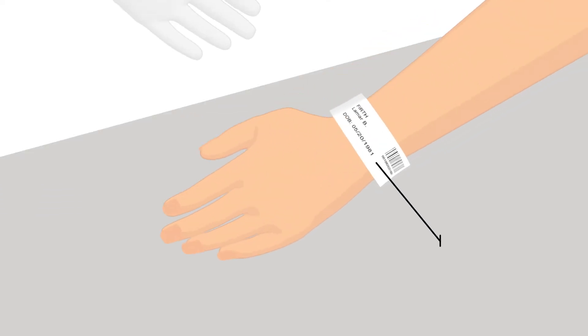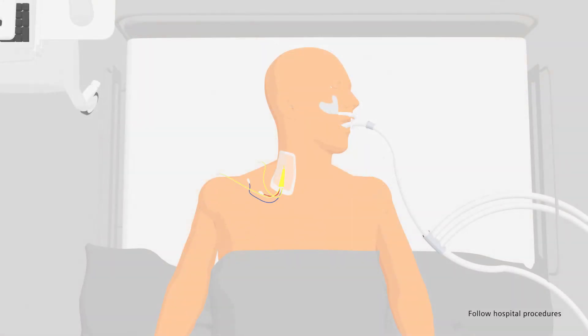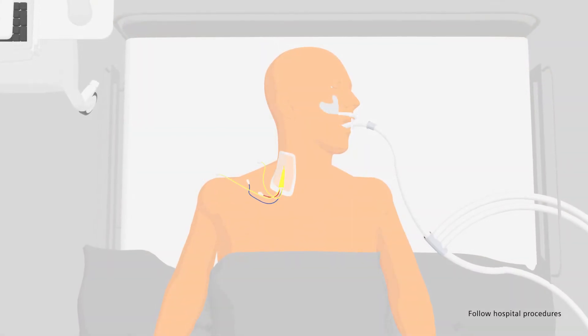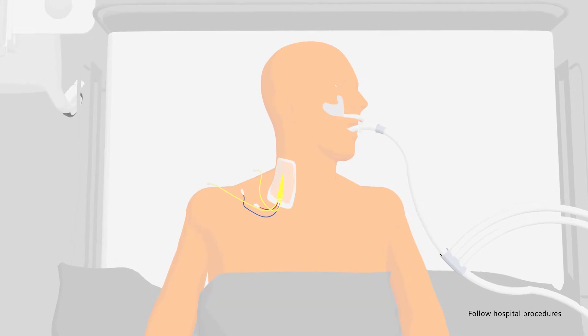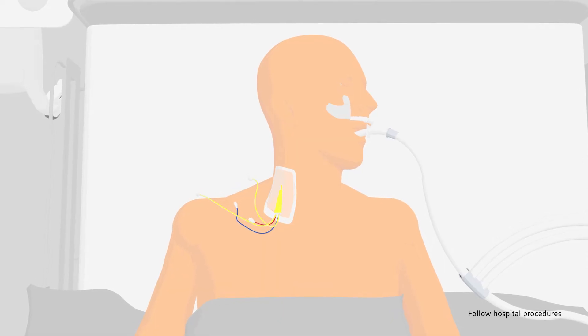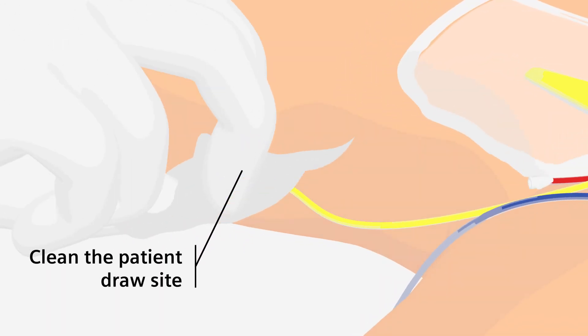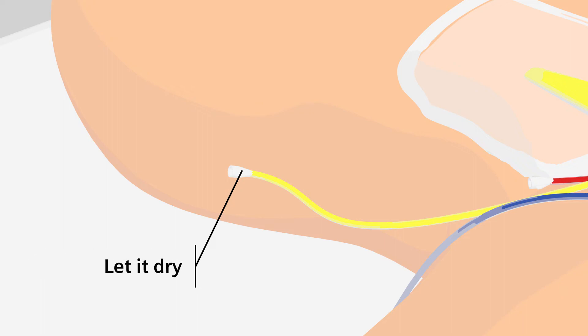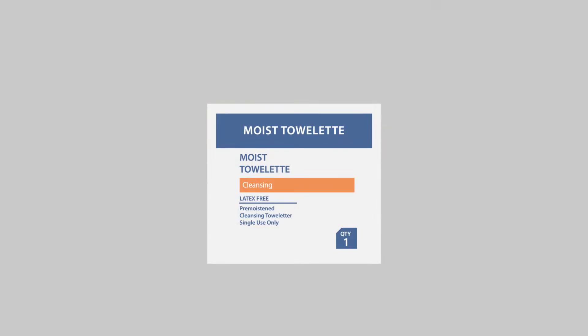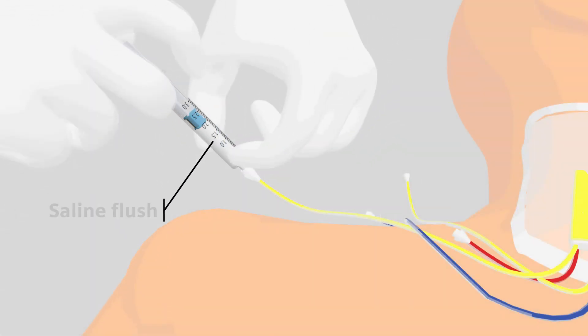Before obtaining the venous sample, confirm the patient's identity. Follow your hospital directives for the proper protocol when obtaining a blood gas sample by venipuncture, or from either a central line or a pulmonary artery catheter. Clean the venous blood draw site or the central line cannula port and let it dry. Do not use a cleaning wipe that contains quaternary ammonium substance, such as benzalkonium, as it may affect the electrolyte parameters reported, particularly sodium.